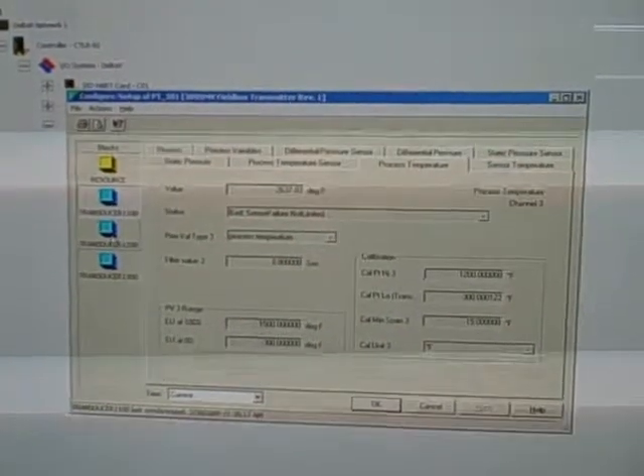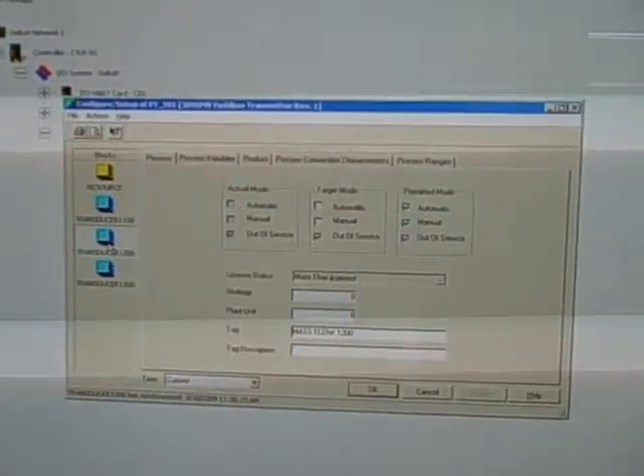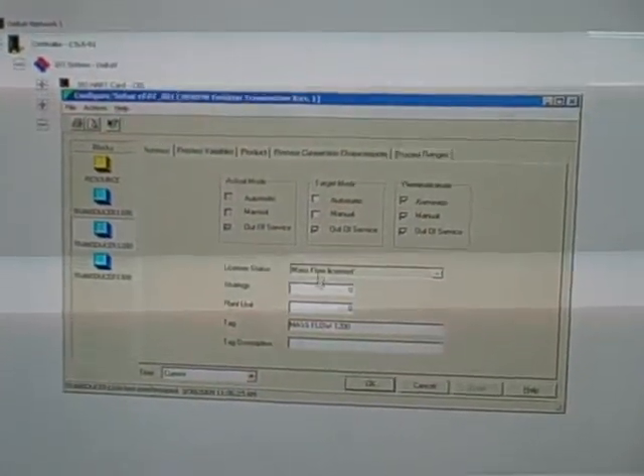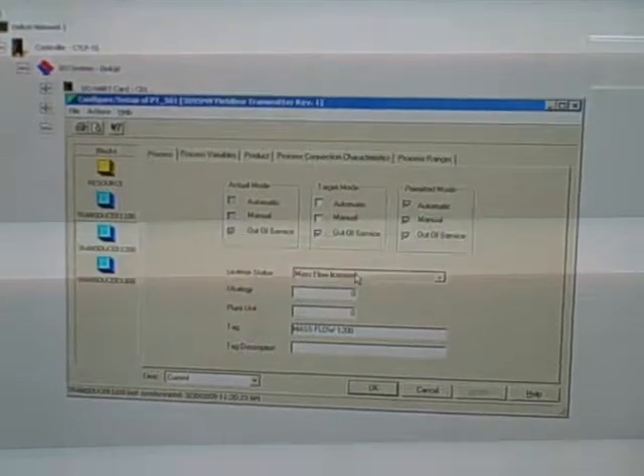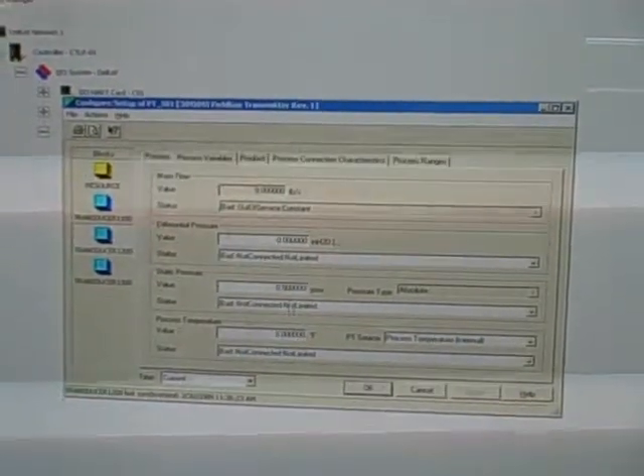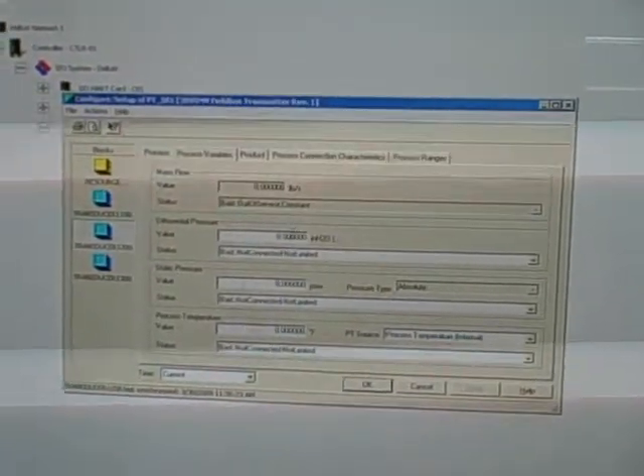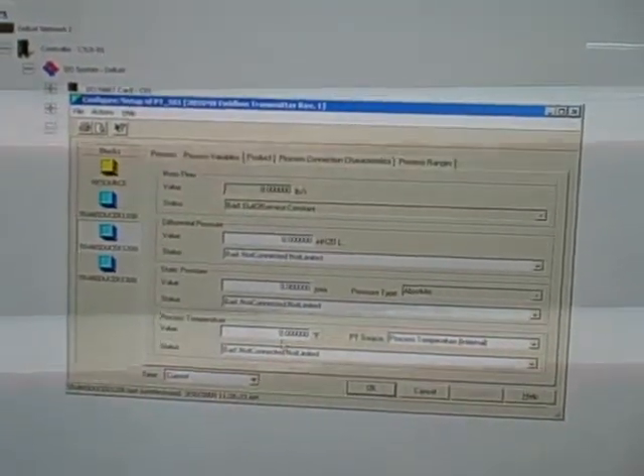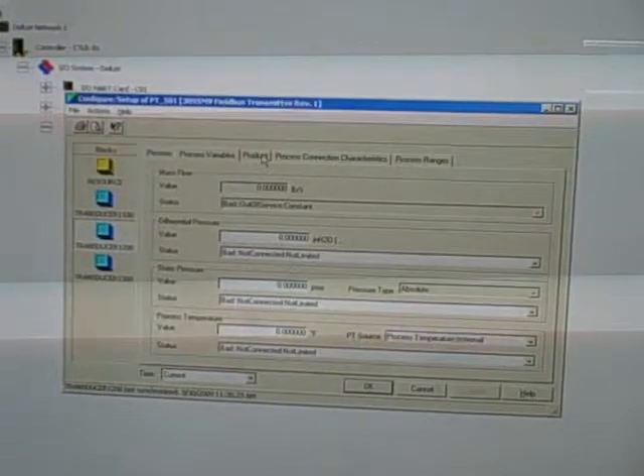If we go to the next transducer block, this is where we actually calculate mass flow rate. It takes in the process variables: differential pressure, static pressure, and process temperature.